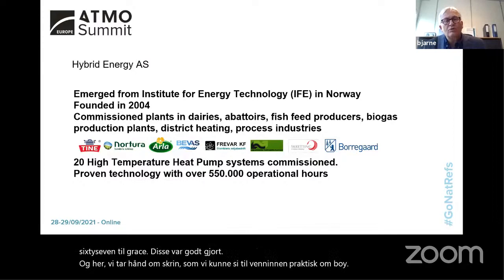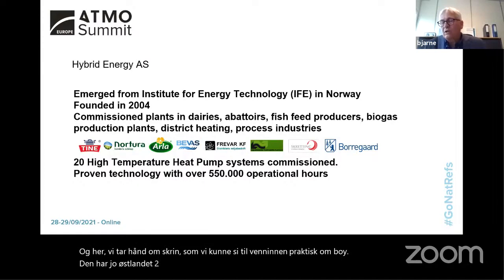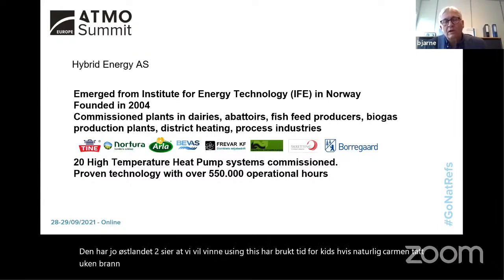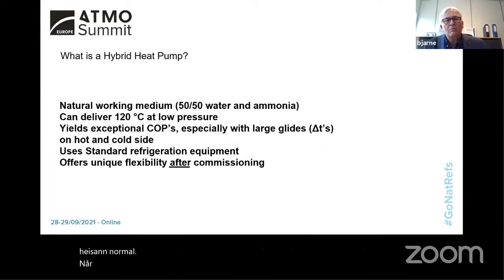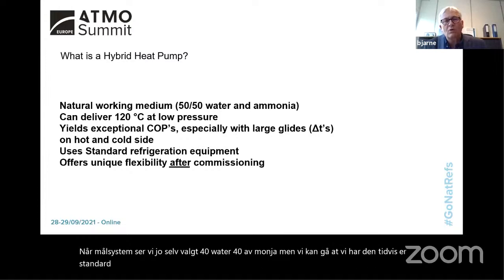I just wanted to say that you've been using this hybrid heat pump. It's not very common that you can blend water into the ammonia and get the pressure down, and still use the compressor as a normal system. So we use about 50% water and 50% ammonia, and we can go up to 120 degrees with the standard refrigeration equipment, which all dairies know from before.